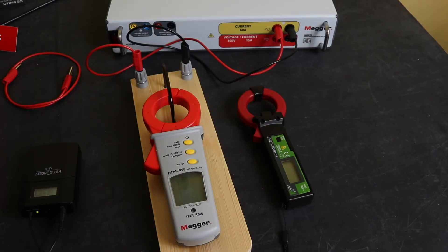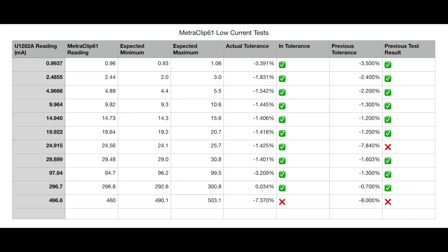Take a closer look at the MetraClip61 test results now. The previous tolerance, you can see that the 25 milliamp was out of spec with a minus 7.8% tolerance. With this test setup, I've got an in-tolerance result, so that is a bit better. The very last result at 500 milliamps is still out of spec.